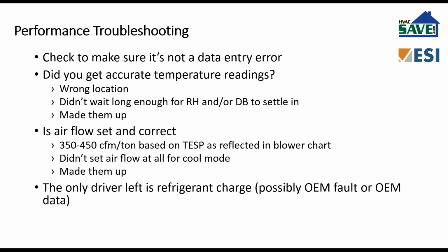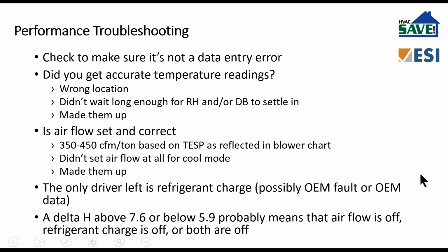Once that's done, then you'll have to rerun through the performance verification process. Now it's possible you could find an OEM fault or OEM data, a bad TXV valve, maybe the blower chart's wrong. All those things will also be uncovered. Okay, doesn't mean that it'll pass the utility program, but you certainly can isolate it down to an OEM fault as opposed to a contractor process fault.